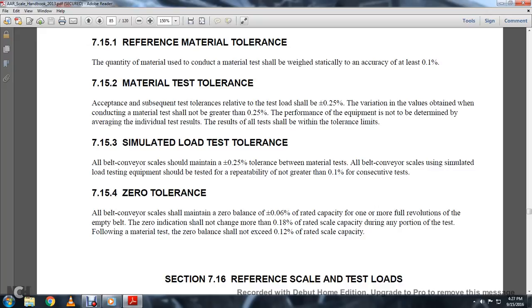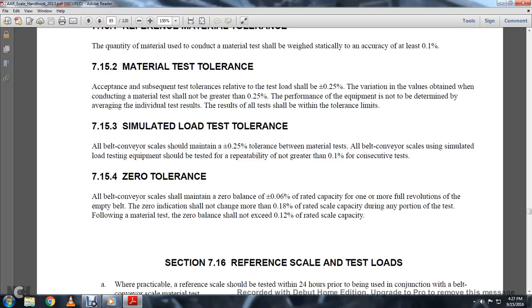All belt conveyor scales simulated load testing equipment should be tested repeatedly with no greater than one one-hundredth of a percent for consecutive tests. A belt conveyor should be maintained with a zero balance of 0.06%; the empty belt zero indication should not exceed 0.18% of rated capacity during any portion of the test. Following a material test, zero balance should not exceed 1/200 of a percent of rated scale capacity.